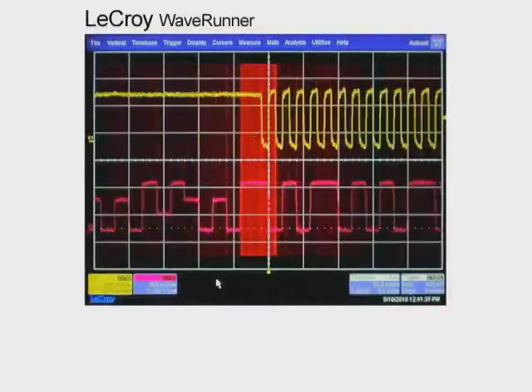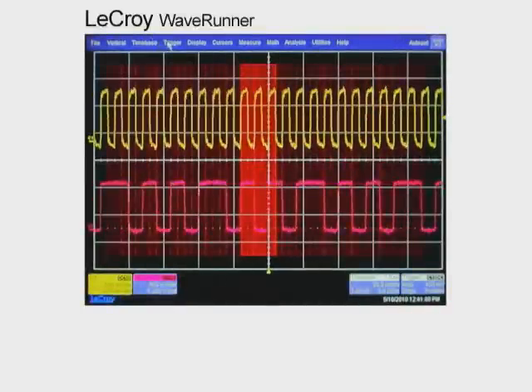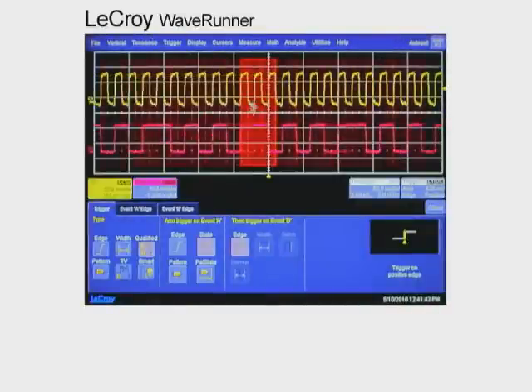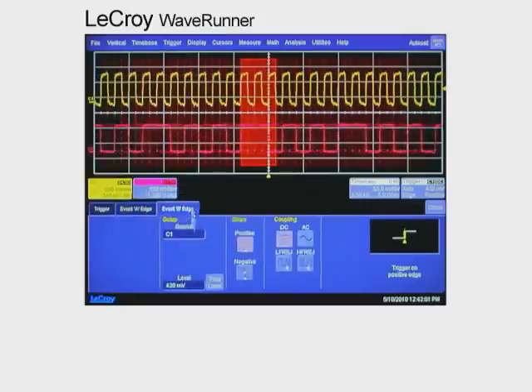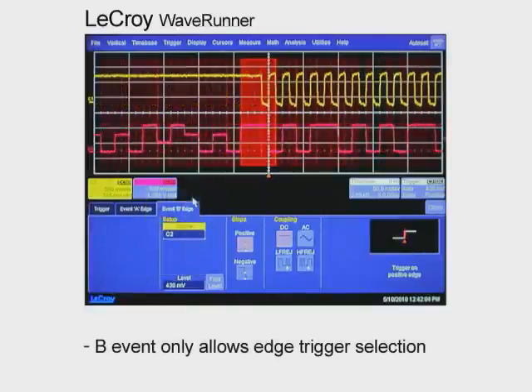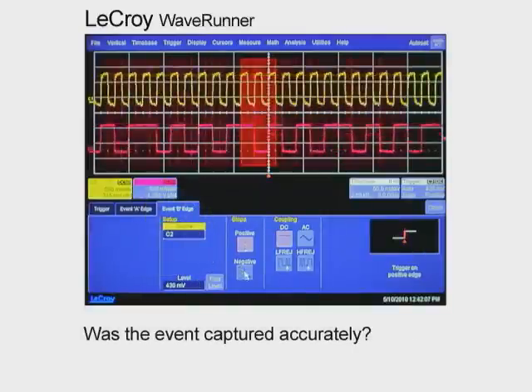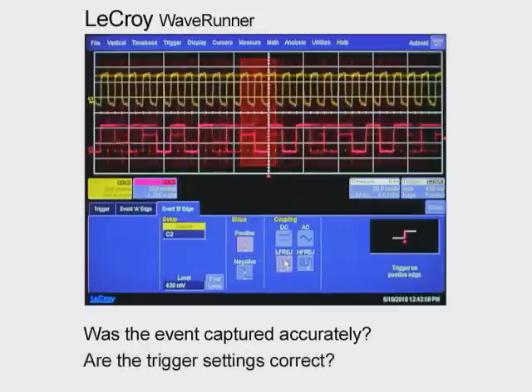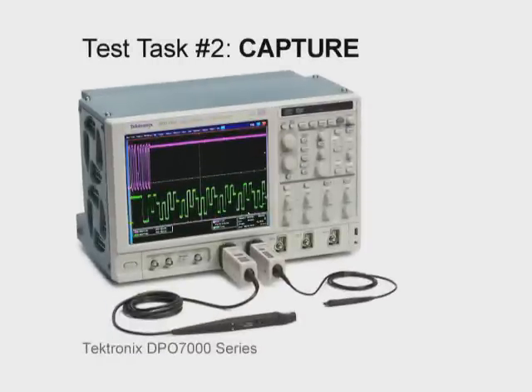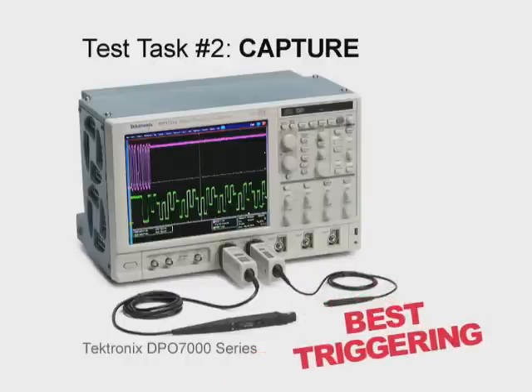Now let's try the LeCroy WaveRunner. Here we've captured the clock signal with a standard edge trigger, but we're having a difficult time looking for a transition timeout trigger for the B event in its trigger system. It looks like we can do a qualified AB trigger, but the B event is only allowing us to select an edge trigger. How do we know this captures the event accurately? The LeCroy trigger system leaves many questions unanswered. After performing test task number two, it's easy to conclude that the Tektronix DPO7000 has the best trigger system for capturing complex signal anomalies.